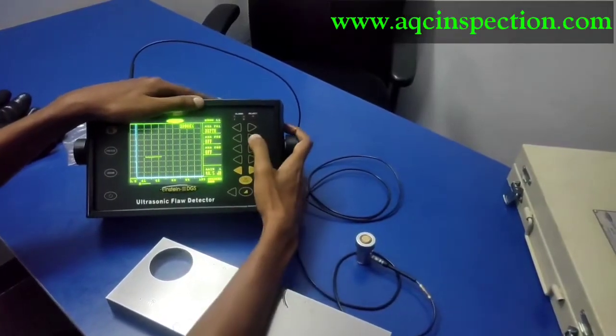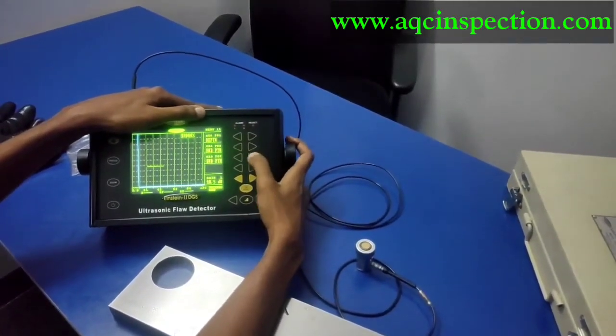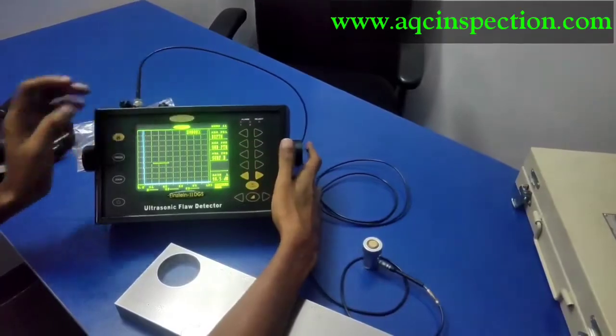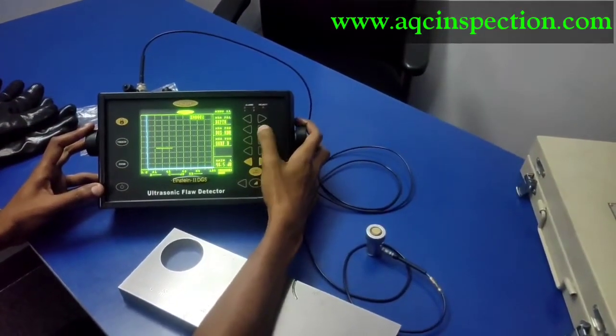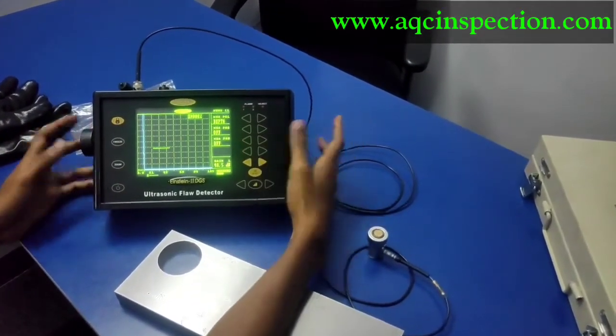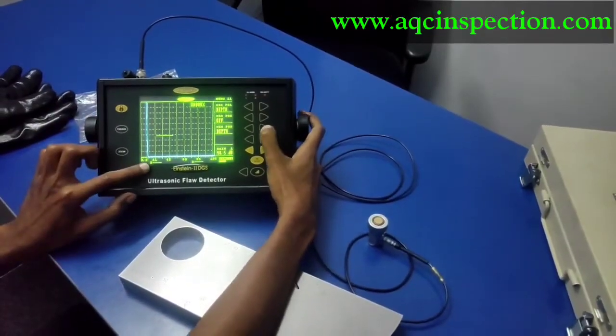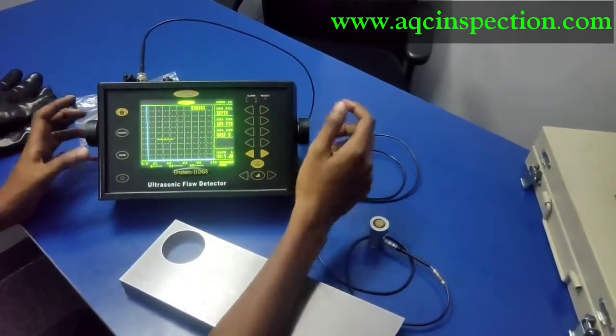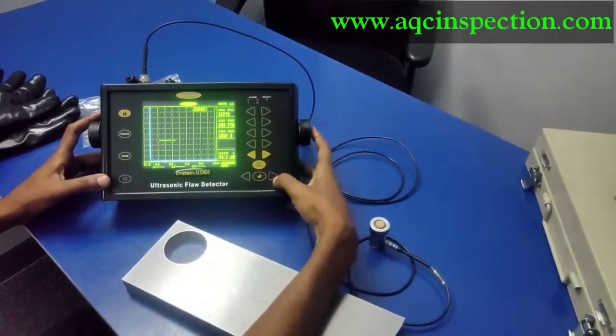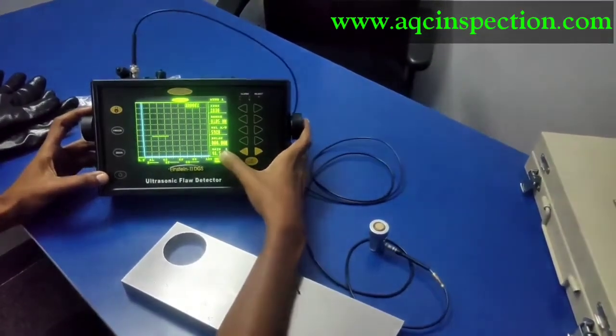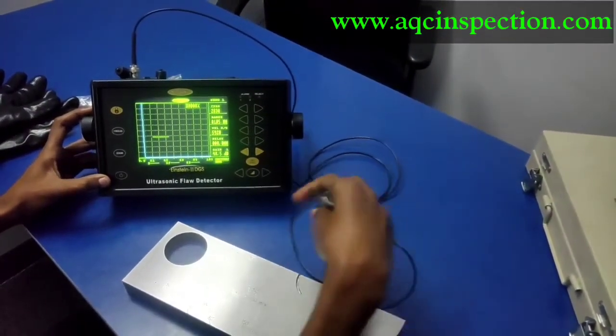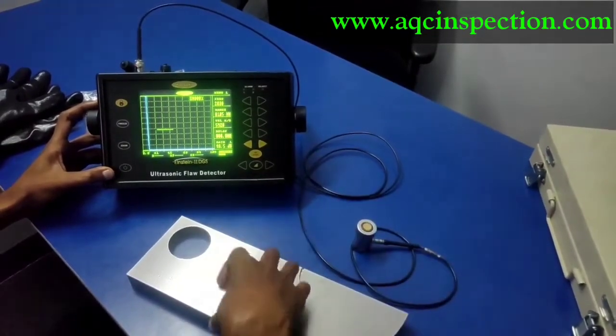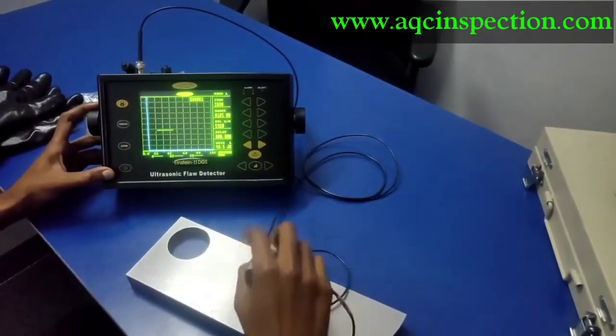You can change the menus according to your preference. When you are using an angle probe, you can use this. Using a normal probe, you don't want this, you can switch it off, since we are going to see only the depth here. If you are going to use an angle probe, this is a must. Then this option right here is gain, which is going to increase the amplitude of the sound waves which travel from this crystal to this block.